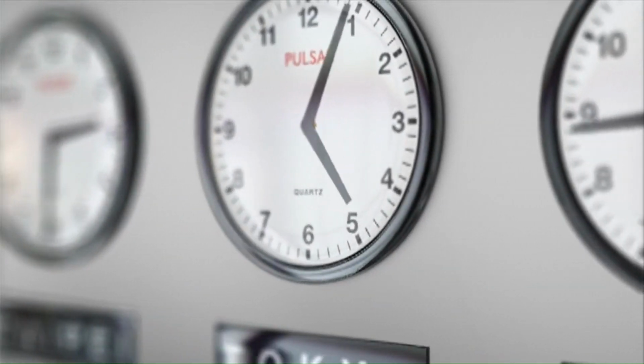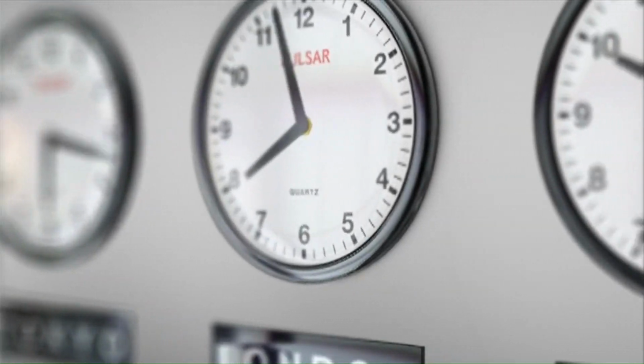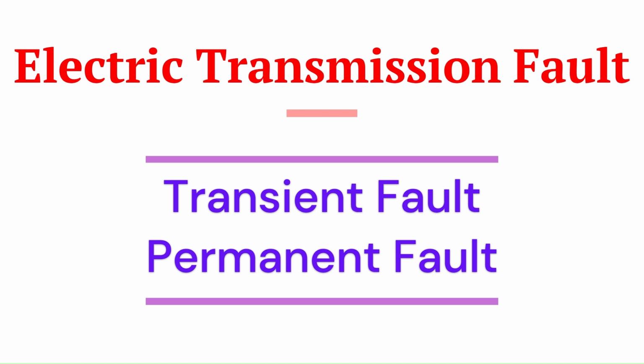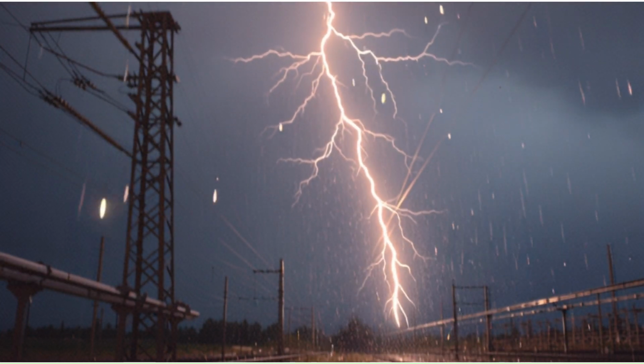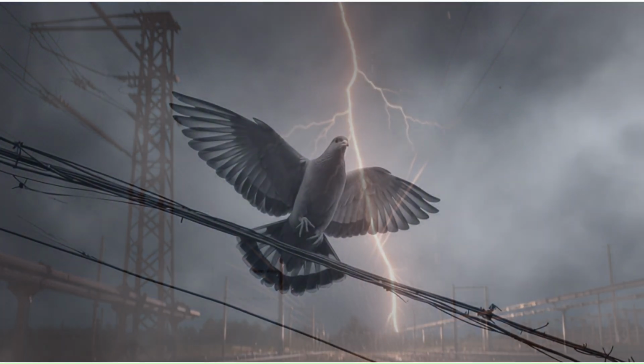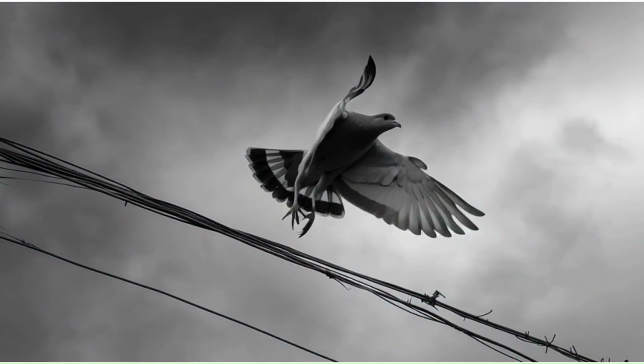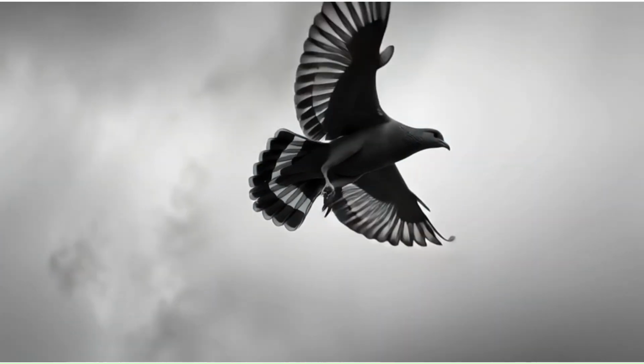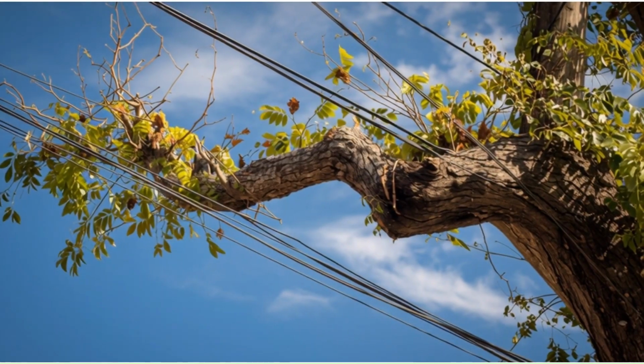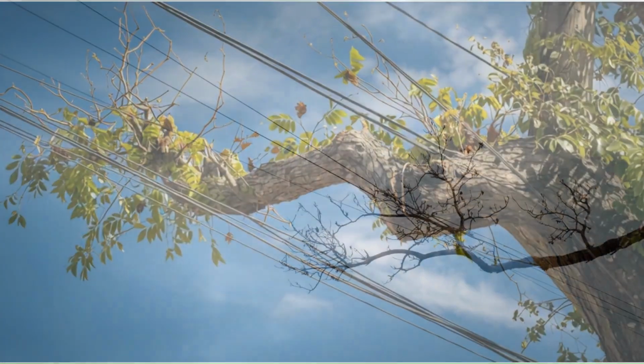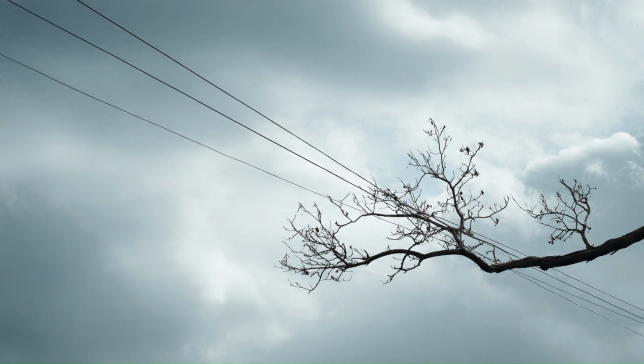Auto reclosing schemes prevent these delays by automatically restoring the power. We can categorize electrical transmission faults into two types: transient fault and permanent fault. A transient fault is a temporary or non-permanent error that resolves itself after a short time. A lightning strike causing a flashover on an insulator is a type of transient fault. A bird or tree branch can momentarily touch a power line, causing a short circuit that is cleared when the bird moves or the tree branch falls, which is also a type of transient fault.